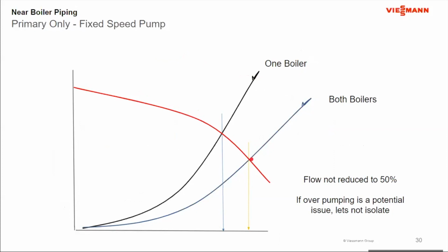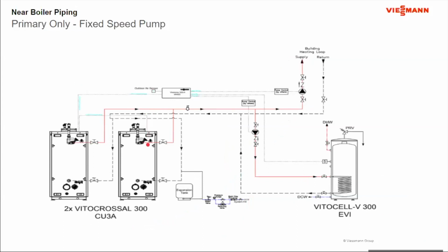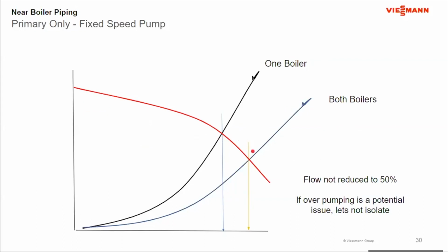The problem with the fixed speed pump is that I'm tied to this pump curve. Let's call this my system curve with both boilers unisolated. I'll have the crossover point at, let's call it, 38 gallons a minute. Now, ideally, if I isolate a boiler, I would love to see that 38 gallons per minute drop to about 18 to 19 gallons a minute, so I am not overpumping the 1 boiler in service. The problem is, if the boiler only has about 1 foot of head loss across it, when I go from both boilers to a single boiler, the curve barely budges. So that 38 gallons per minute is maybe 30 gallons a minute, but not a whole lot less.